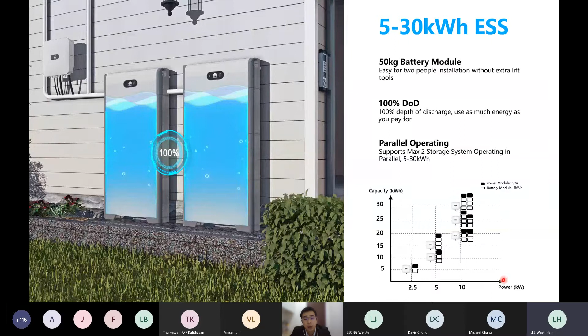Just to highlight, for the installation method you can have 2 types: floor standing as well as wall mount. For the parallel operation, if you look at the graph, the y-axis is the capacity of the battery, up to 30 kilowatt-hour, and here is the discharge power of the battery. The black color is the power module and the white color is the battery module. In this picture, it is a 5 kilowatt-hour capacity, so the discharge power will be 2.5 kilowatt. If you use one power module with 2 to 3 battery modules, the capacity would be 10 kilowatt-hour and 15 kilowatt-hour, and your discharge power will be 5 kilowatt. Unlike if you parallel 2 power modules into one inverter, then you have a higher power rating, like 10 kilowatt discharge power here.